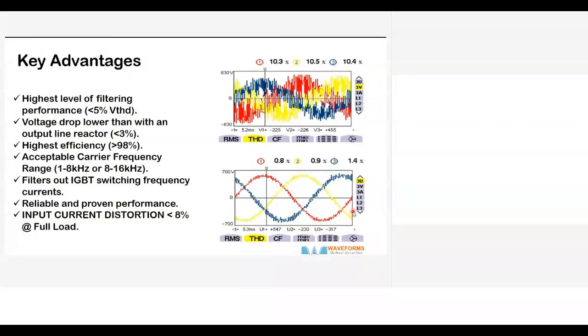So it has the highest level of filtering. The voltage THD is normally 30%, and it is reduced to 5%. The voltage drop is also avoided because we have a capacitor added to it. It's a smaller capacitor, and it has high efficiency. The carrier frequency range can tolerate 1 to 15 kilohertz, so it filters out the switching frequency current of the IGBT.